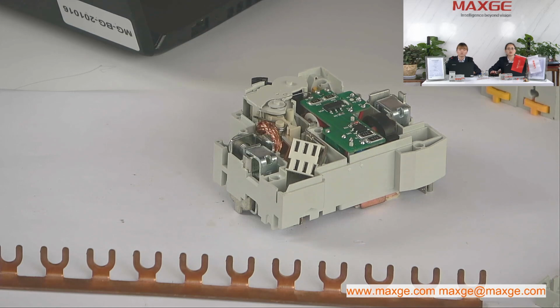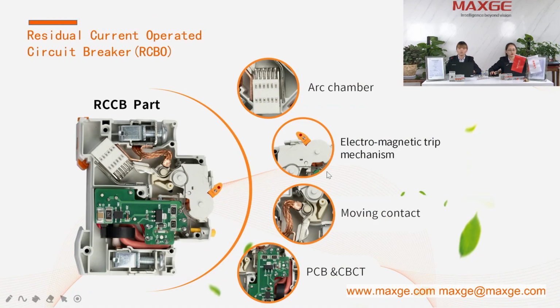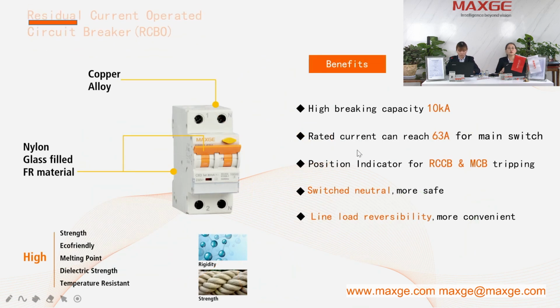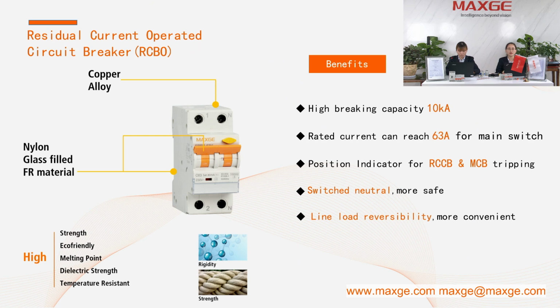From my above introduction of the EPBR-63 series RCBO, we can conclude as follows. With our high-quality material of plastic and metal parts and its reasonable design, we can reach a high breaking capacity of 10 kA. The rated current can reach up to 63 ampere for our main switch. Also, with position indicators for RCCB and MCB tripping separately. With the switched neutral phase, it is safer. Also, it has line load reversibility, more convenient and more welcomed by our customers.